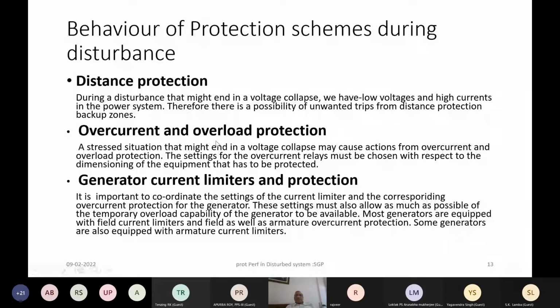So one of the recommendations for the application of line protection is you should have main 1, main 2, both protections to be distance relays, and overcurrent protection as a backup should be provided only for earth fault. Phase overcurrent protection is actually not to be provided for 400 kV lines. Some also critical 220 kV lines can trip in an undesirable fashion.